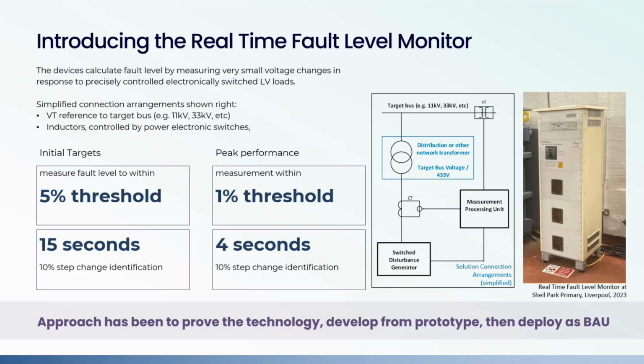Because the device is switching the inductive load itself, it knows precisely what time and where to look on that voltage waveform, so it is able to see those very small voltage responses. It also has built-in CTs, so it's got the change in voltage and the change in current. It can then use that relationship to calculate the network impedances at that part of the network, and from that it's able to calculate the fault level. So it's capturing fault level through real network measurements and observations.